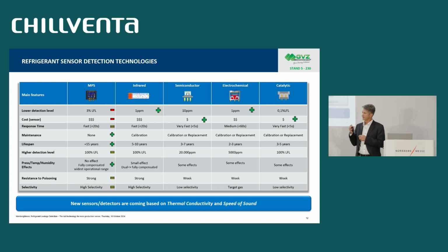And the task is to check concentration closest to the dangerousness, not micro leakages. On the positive side, as we said, long life, maintenance-free, calibration-free, and a wide range of operating temperature.